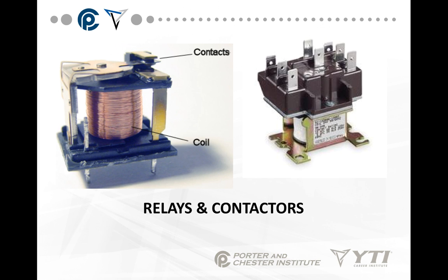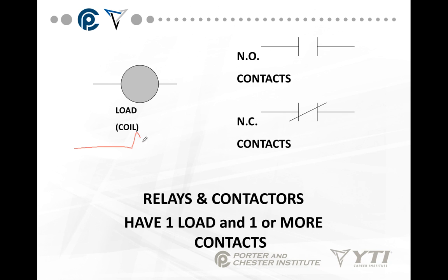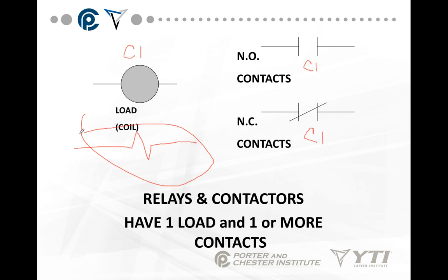Relays and contactors — we'll talk much more about these in the future, but a relay is basically an electronic switching device that has contacts and a coil. You'll see them on your circuit boards. The coil is a load, and it's drawn either as a circle or as a relay coil symbol. The key is: if the coil is labeled C1, the contacts controlled by it are also labeled C1 — that's how you tell they go together.